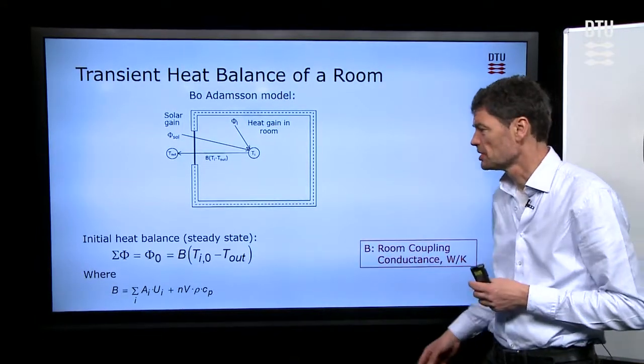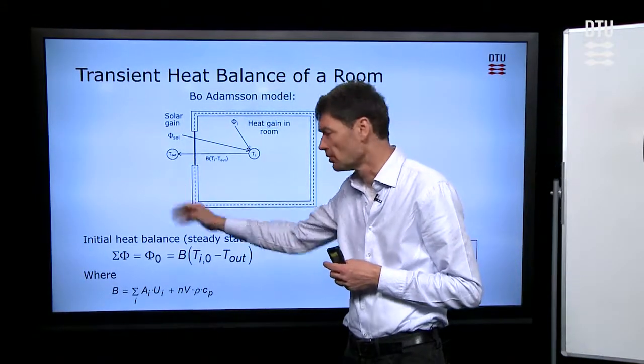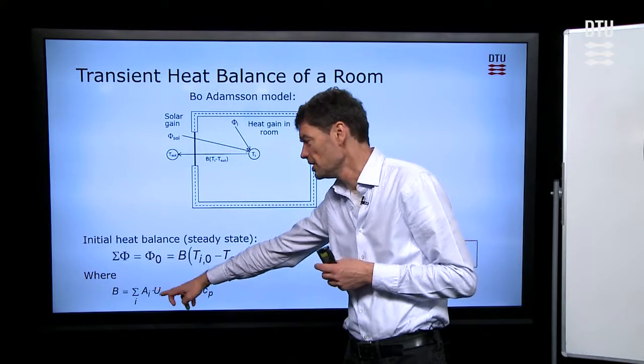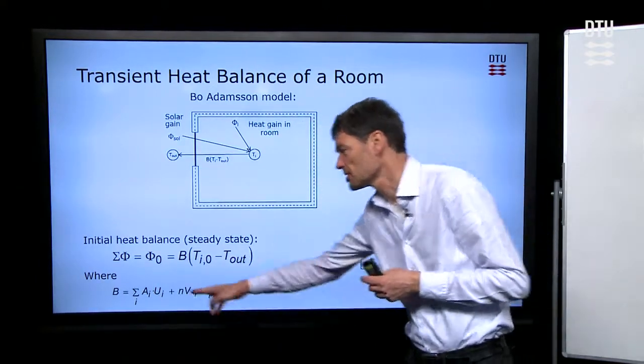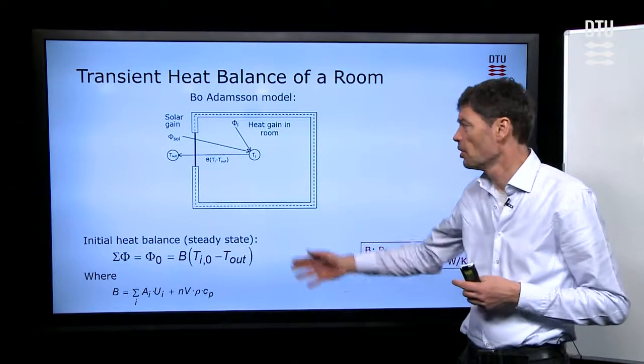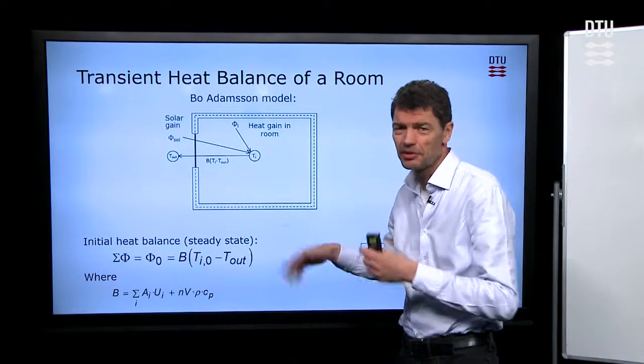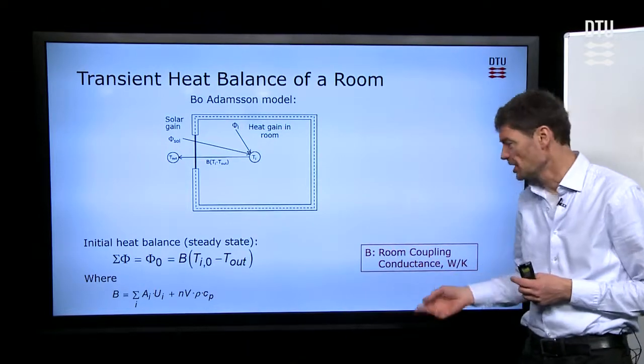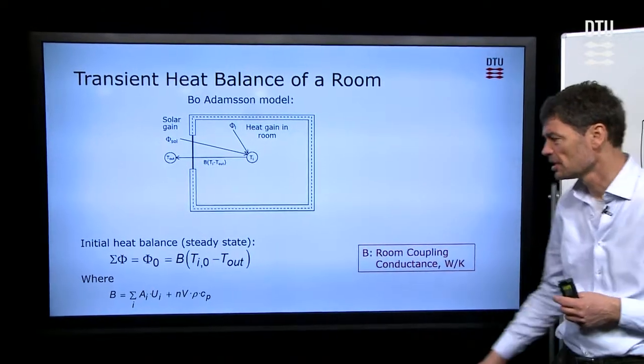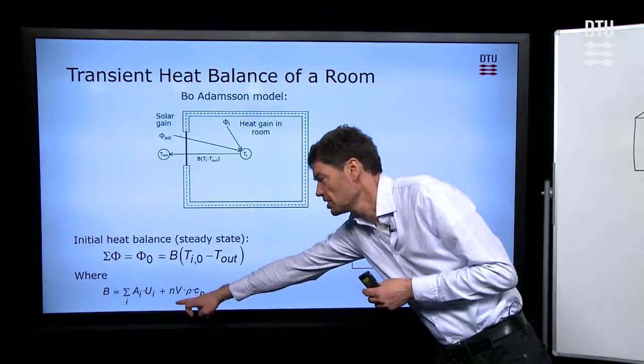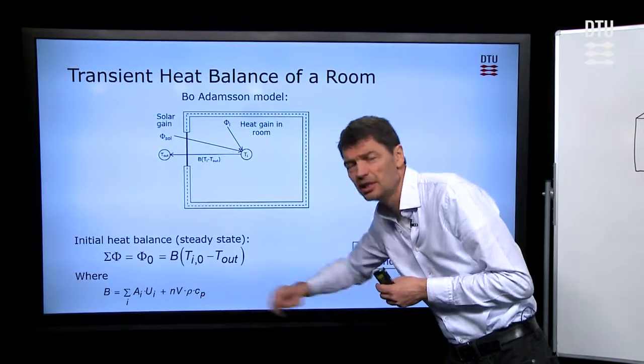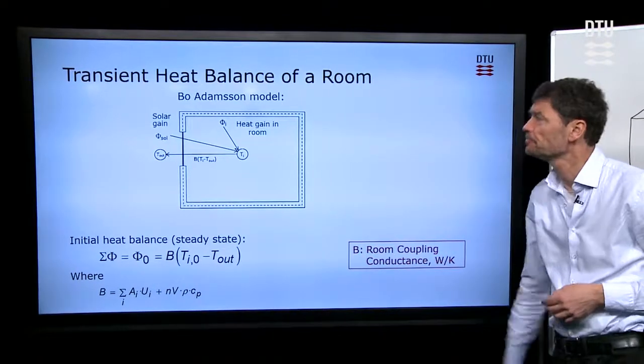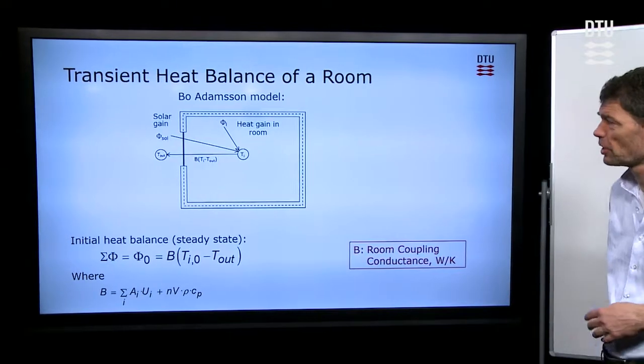The room coupling conductance comes from heat transmission through the walls, where we multiply the area and the U values for all walls and sum them up. And also, we have heat transmission because of ventilation heat loss, which we calculate the contribution for ventilation to the room coupling conductance by the last term here: air change, volume, density, and heat capacity of the air.